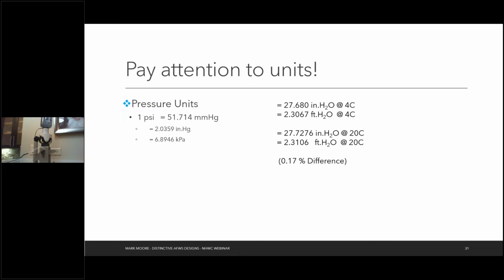So one thing to be aware of for units is that most PTs are going to be measured in PSI. And 1 PSI is 2.3067 feet at 4 degrees Celsius, or 2.3106 feet at 20 degrees Celsius. Again, I promise not too much math, and I promise no exams, so don't feel like you have to know this number. But the most interesting thing to me that we're talking about here is that the pressure of water changes based on its temperature. If it's colder water, it's going to be slightly more dense, and you get a smaller amount of water per unit of pressure. Whereas hotter water is slightly less dense, and so you get more water per unit pressure.